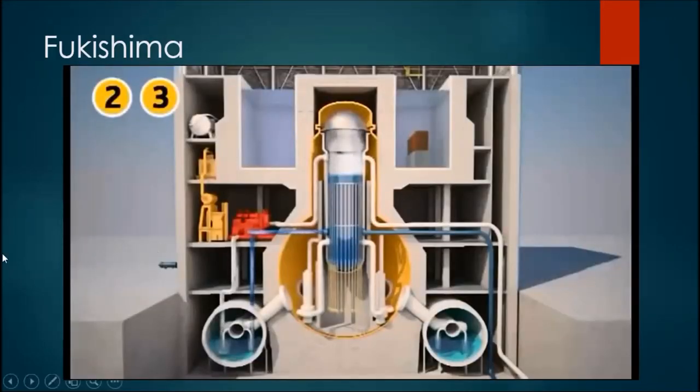On units 2 and 3, the batteries were still operational. They operated some of the valves. The turbine-driven pumps ran for nearly 24 hours and then stopped. The cores were no longer cooled. The water got in and stopped the diesel pumps.